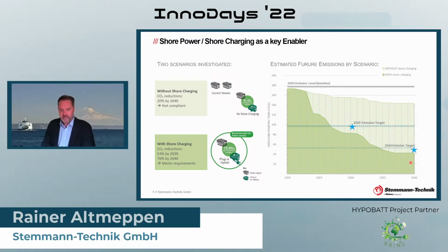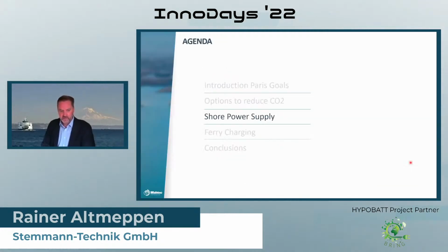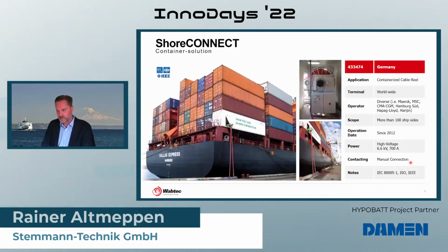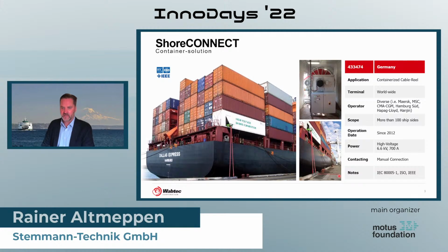To give you some insight into the complexity, let me introduce the shore power supply systems—the standardized systems we have today for charging container vessels, for instance. Here cable reels lower cables from the ship to connect to landside connection boxes, like your own extension cord plugging into a landside supply. We can charge up to 6.6 kilovolts, all standardized per IEC, ISO, and IEEE requirements—the same plug and frequency between 50 and 60 hertz, no problems.